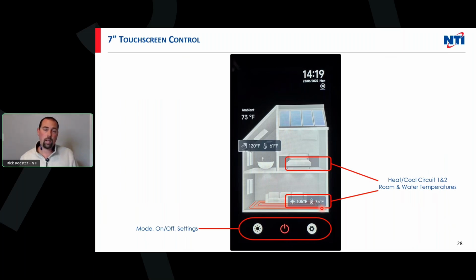We don't necessarily need a buffer tank in every application, although it is recommended. You can run without, and in this case you would take the buffer tank sensor and put it on the return piping going back to the heat pump, and that's how it would control its temperatures. So you would see what our set point is, and then the actual temperature of the water going back to the machine. Depending on the application, we have that ability.